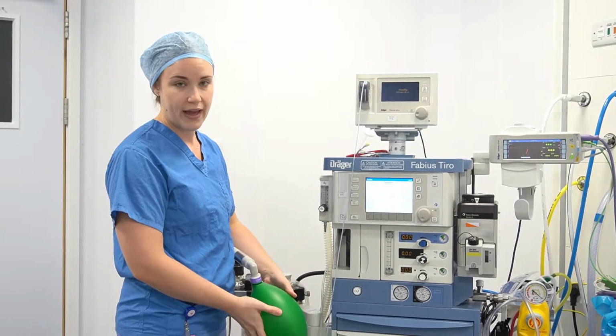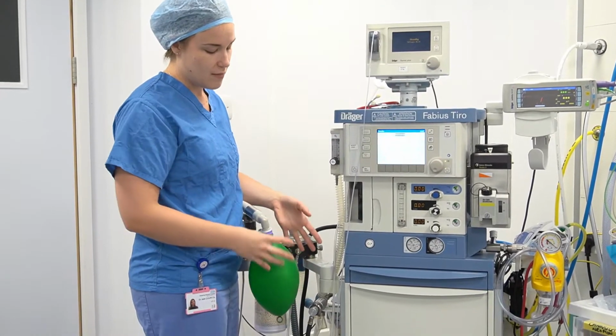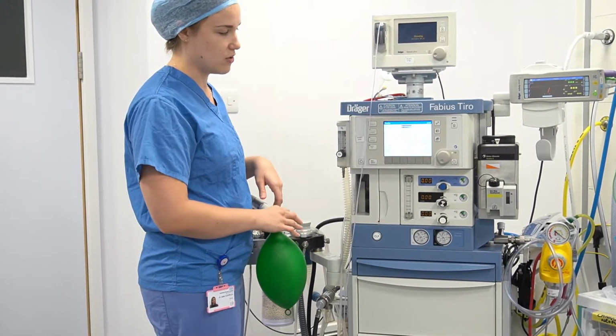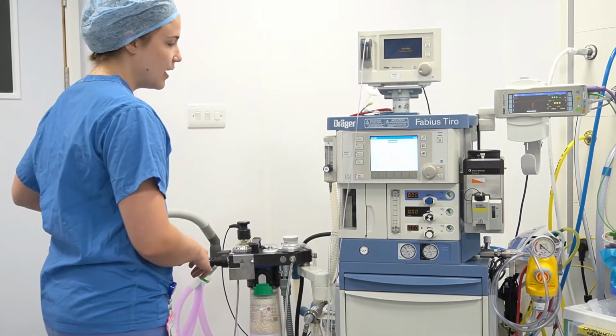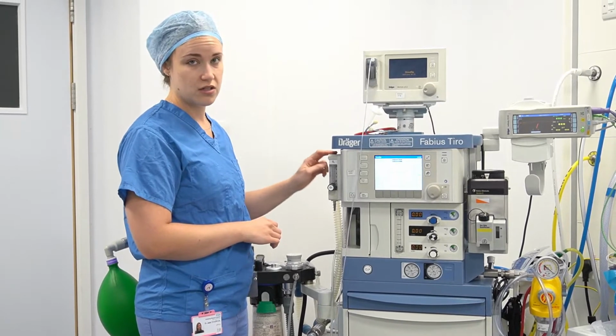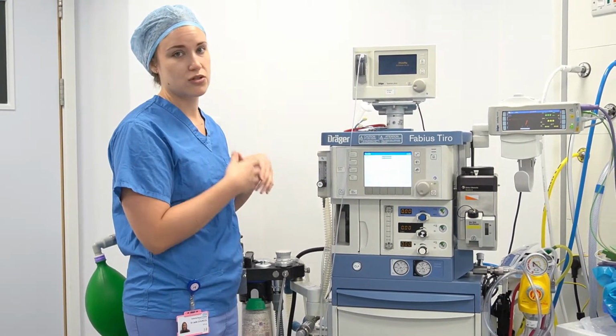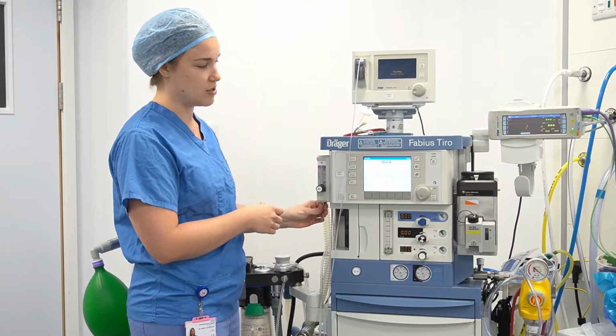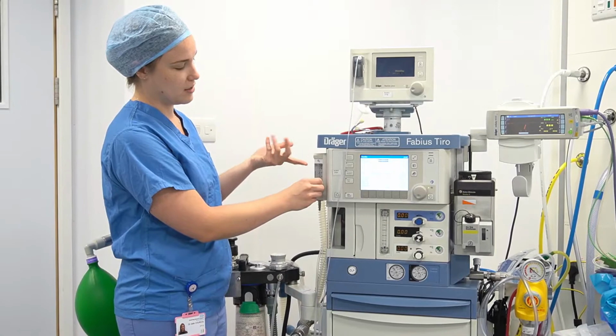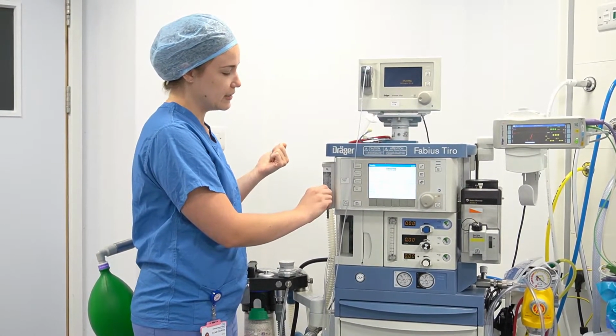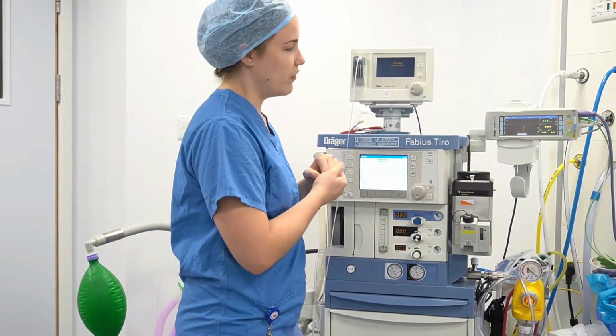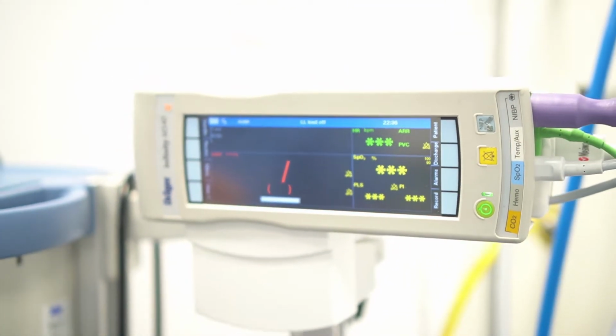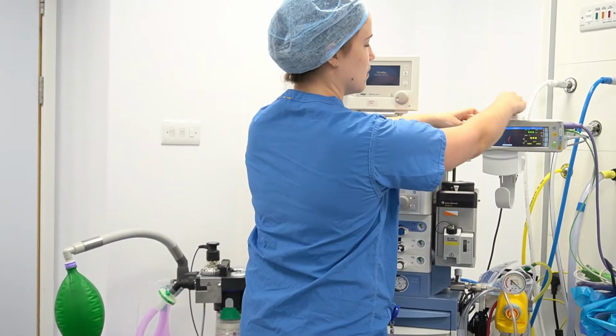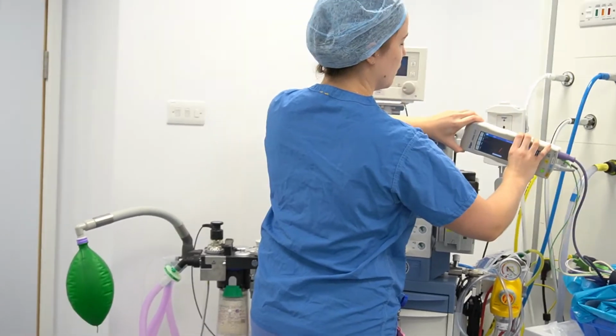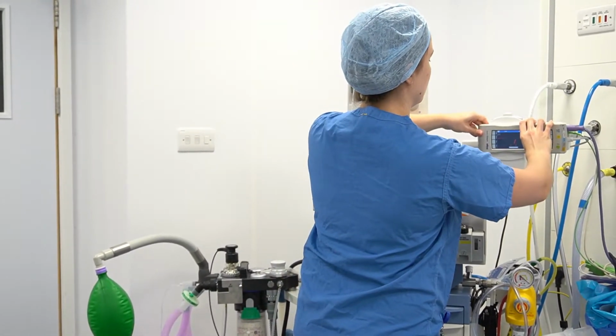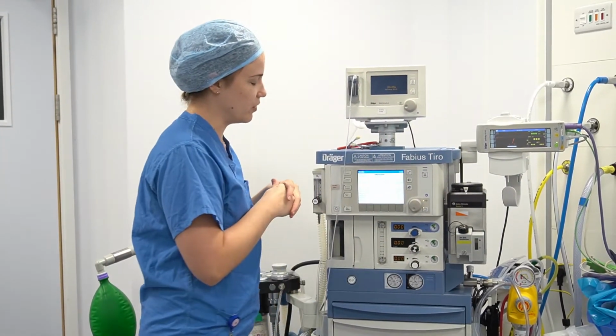You can also have a quick look at your bag. Obviously this test is testing for the same thing, but your bag is not damaged, you can't hear any air escaping, so you know that this is working properly as well. Also, just another thing to mention is your auxiliary oxygen is found over here. Once you connect a patient to nasal cannula or any mask oxygen directly to the machine, you can connect it over here, and then you'll turn it to the flow that you would need. You can also see the brick for monitoring, whichever you connect to your patient, and this can be removed by clicking unlock and taking that off, and then popping that back in and locking it again. And that's your monitoring.